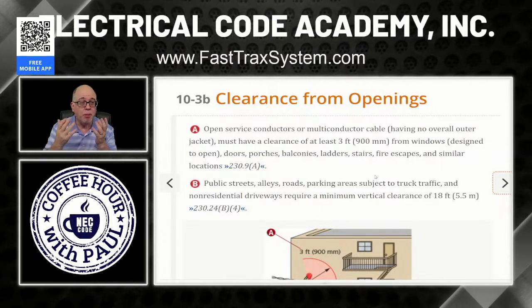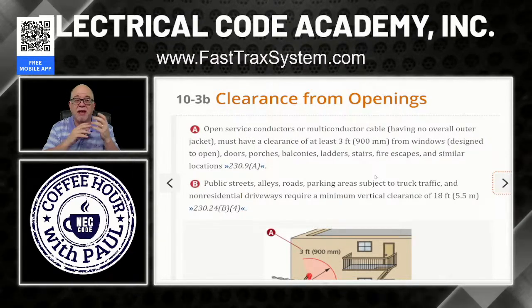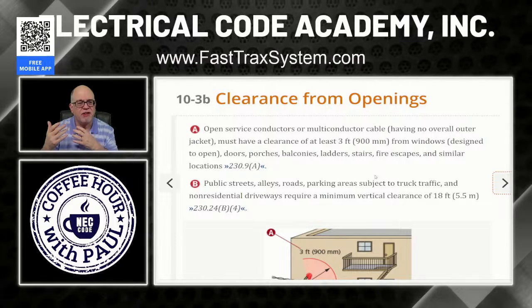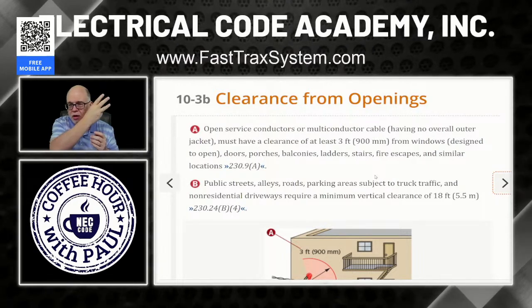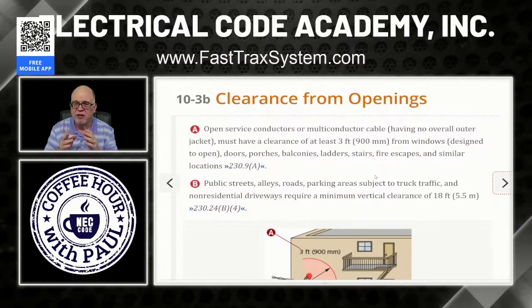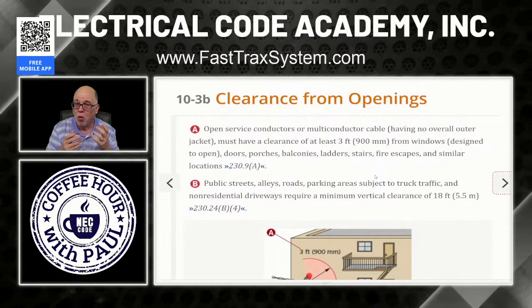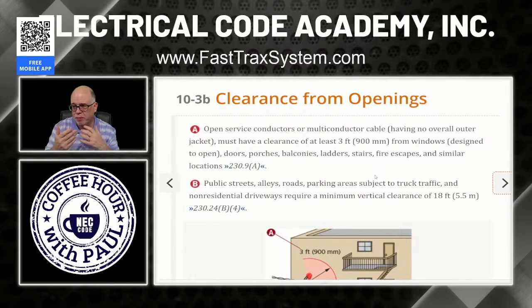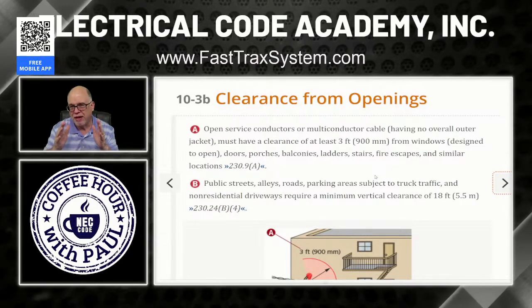We're talking about the open conductors like from a service drop. And once they come out of that bundle, which is a multi-conductor cable, it's plexed at the manufacturer. Once it separates, now you have open service conductors or individual conductors. But in a lot of buildings, you also have steel drops that come down that have separate service conductors that come down. Okay, we call those open service conductors. So the key to this clearance from openings has everything to do with multi-conductor cables without covering or jacket, or the individual service conductors as they may come out of that assembly, even at the point of attachment where they separate. Those are individual service conductors, and we have clearances we have to keep away from. So let's look at that.